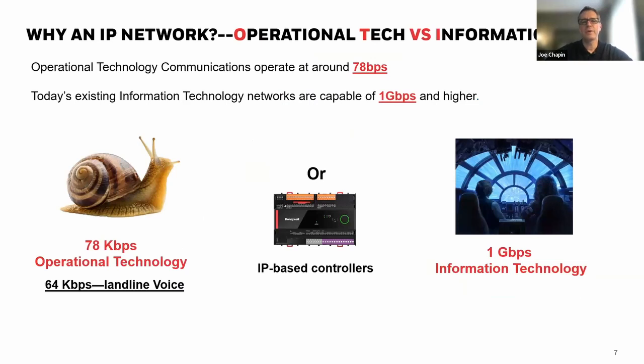Now, IP networks, Internet Protocol networks, that's the standard language of the internet. And here's why IP controllers are so much more desirable than your standard controllers. If you look at standard operational technology like BACnet, Modbus, FOX/FOXS, they typically run around 78 to 80 kilobits. That's about the internet speed of 1995. So if you're on one of those connections, it's like surfing the net from a 1995 internet connection.